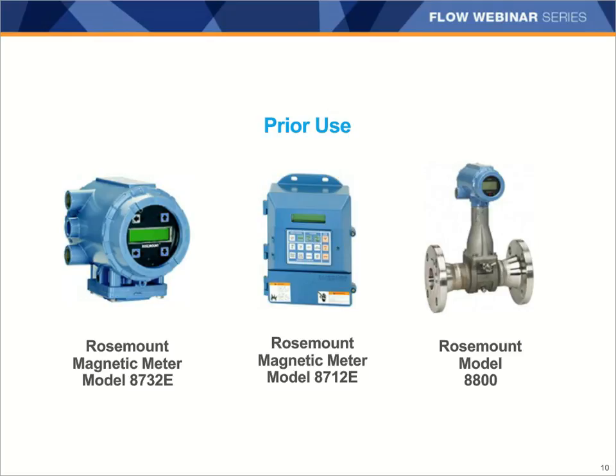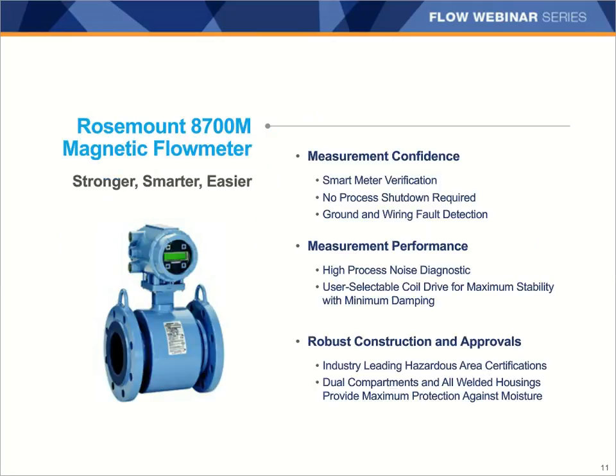So let's talk a little more specifically about the Rosemount mag meter. The Rosemount magnetic flow meters can be ideal for many chemical applications. They have a broad range of liner and electrode materials. They have built-in diagnostics, including grounding and wiring fault detection, process noise reduction, and smart meter verification, which checks the health of the device. Rosemount also offers the 8700M with industry-leading hazardous area certification. It has fully isolated electrodes that enable IA protection type, has glass headers for secondary containment, and industry-leading temperature codes for all approvals.